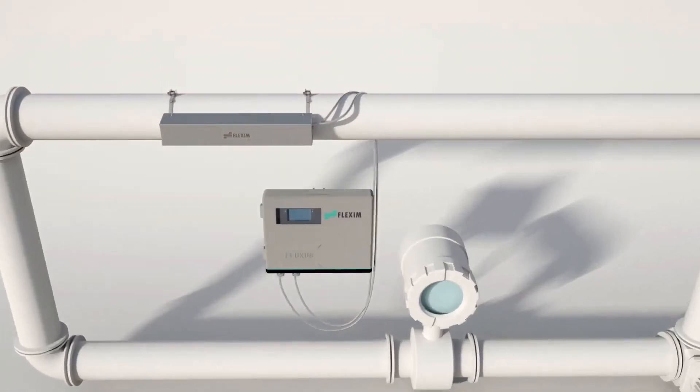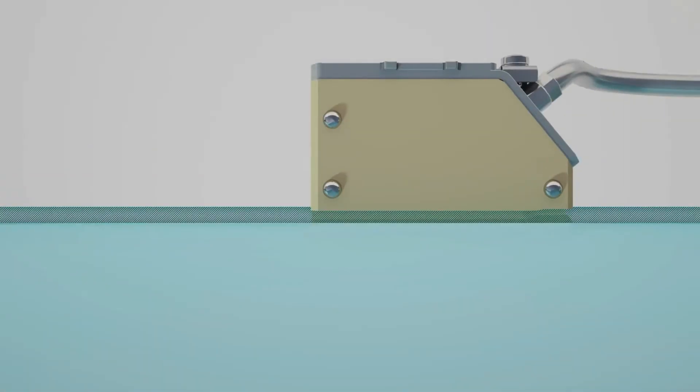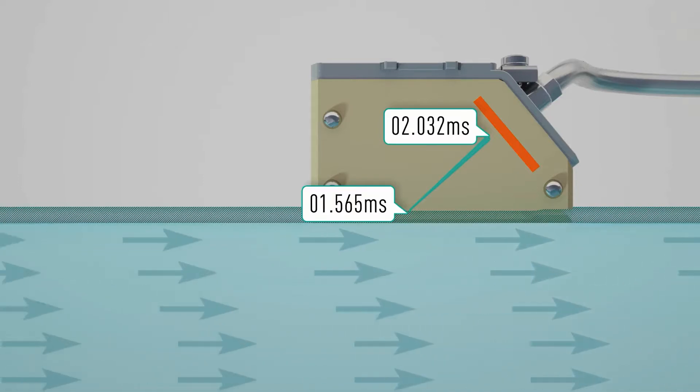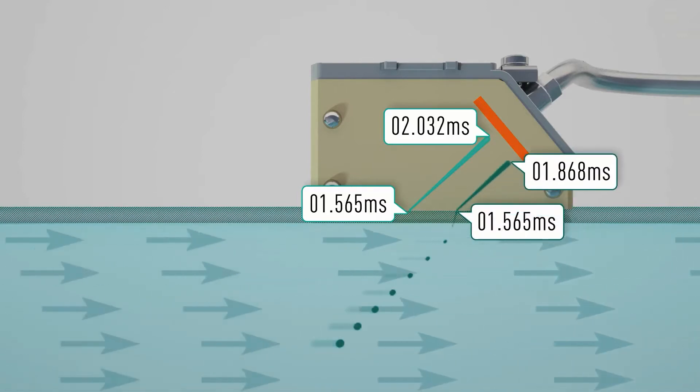Let's take a closer look at how non-intrusive ultrasonic flow meters work. The ultrasonic signal travels through the fluid, enters the transducer wedge, and contacts the piezoelement. It is important to understand that the time the ultrasonic signal spends traveling through the fluid always stays the same, independent of the fluid velocity.